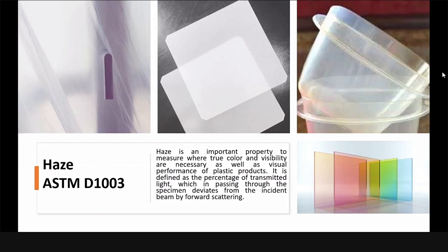So there is a thing. It is a little different from other simple measurement. Here we need to measure the sample over white and over black. So every sample we have to measure two times. One time we have a specific white tile in the sample port, and then we have a black trap on the sample port.